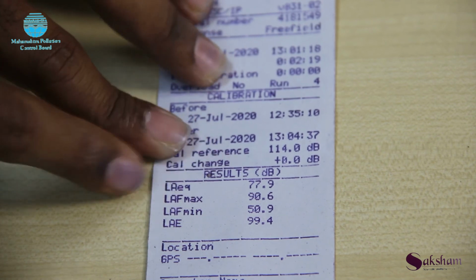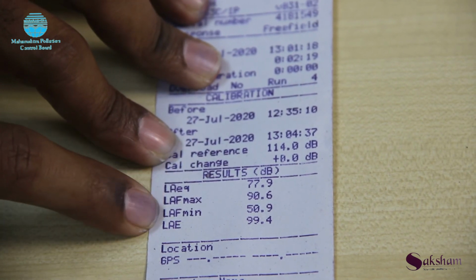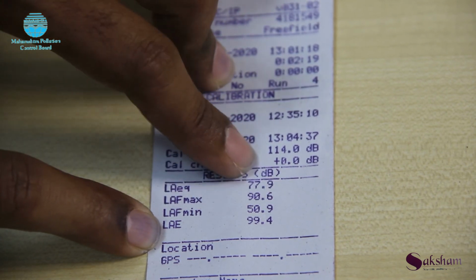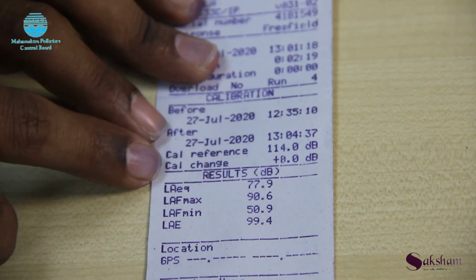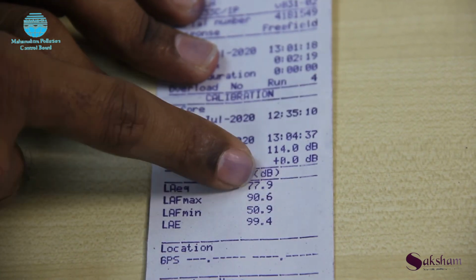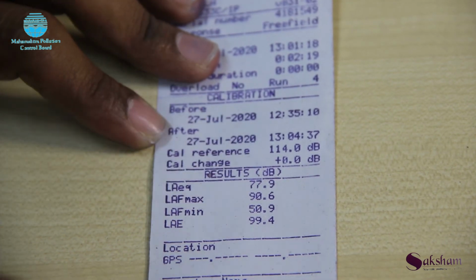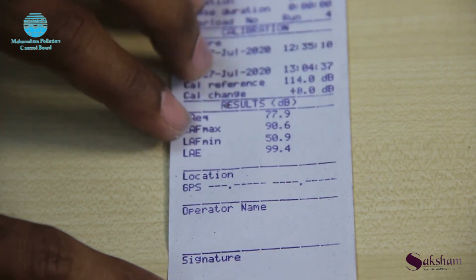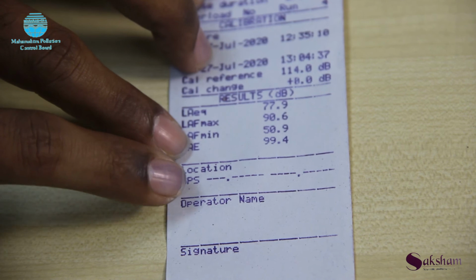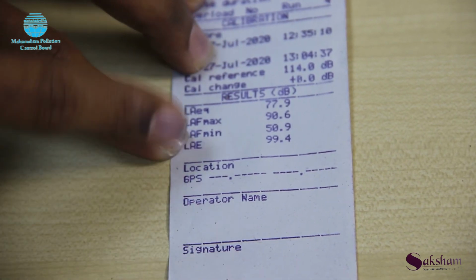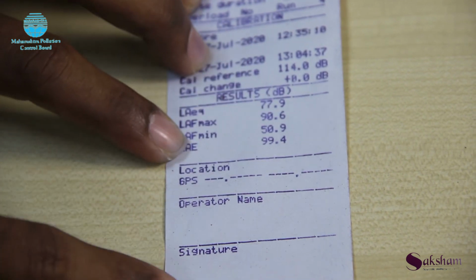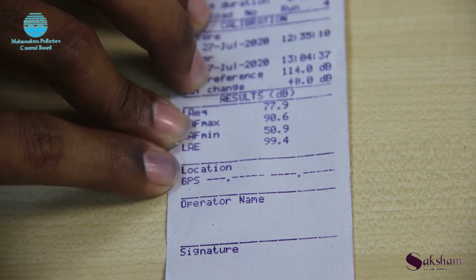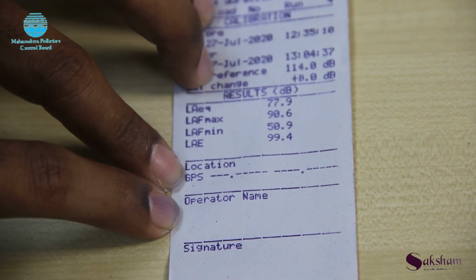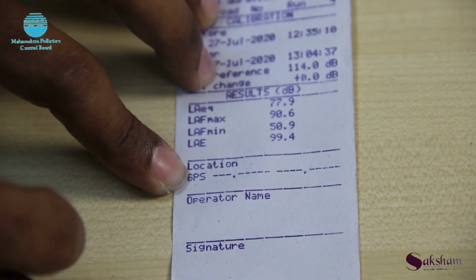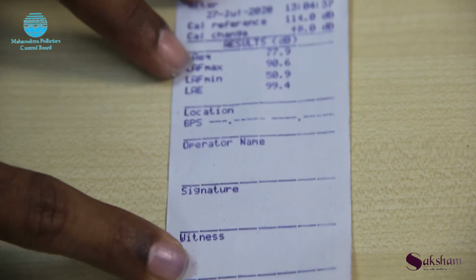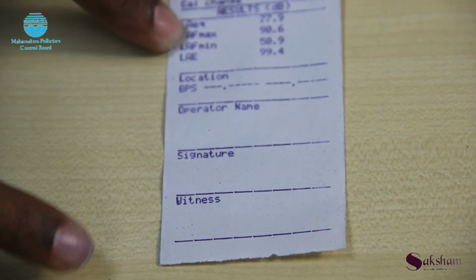Below, in the result, it is showing LAeq, LAF max, LAF min and LAE. These readings are all in decibels. In our case we require LAeq, that is the average reading which is required. On this basis only we take action against the party. Below that, in location, if we are taking the reading outside of a closed room, it shows the longitude as well as the latitude of that location automatically, because our sound level meter has a GPS. Then below, the operator name, signature and witness we need to write manually. In this way we get the printed format.